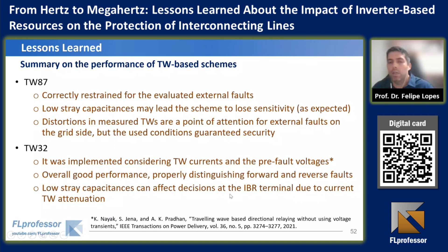We implemented also the overcurrent element based on traveling waves, and it showed to be very promising. And just for verification, it was studied also at the IBR terminal. It presented an overall good performance for higher stray capacitance at the IBR terminal. We know that the original application does not consider the application of such a function at the IBR terminal, but we are interested to see how critical the function would be if applied at the IBR terminal. And it presented an overall good performance, but low stray capacitances reduced the scheme sensitivity at the IBR terminal as expected.